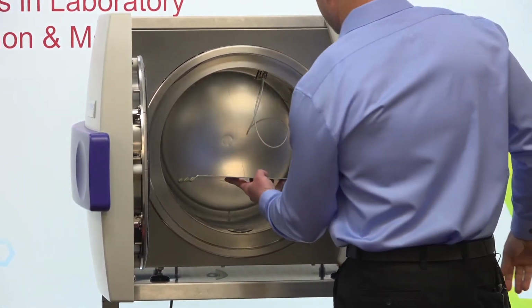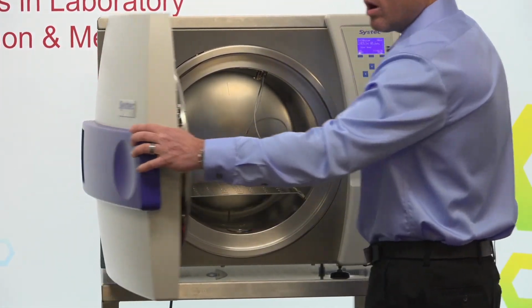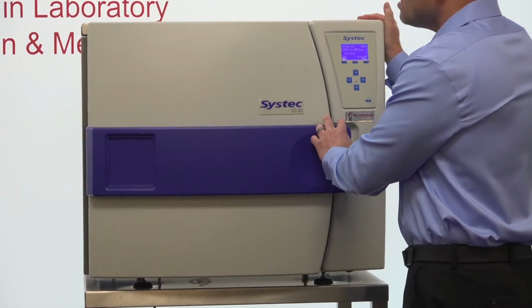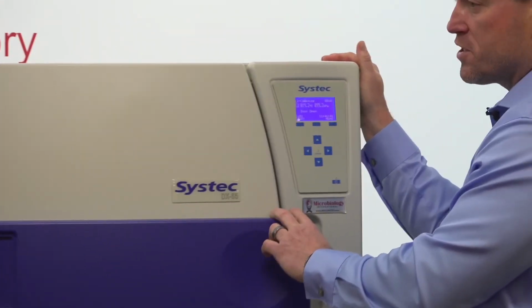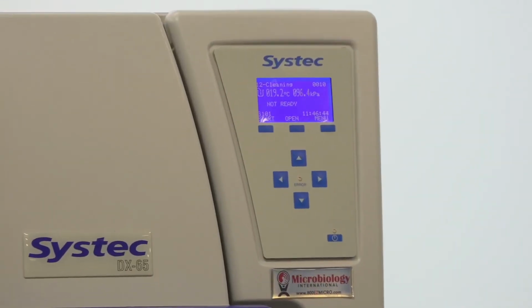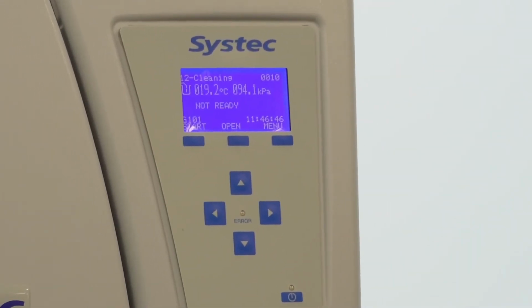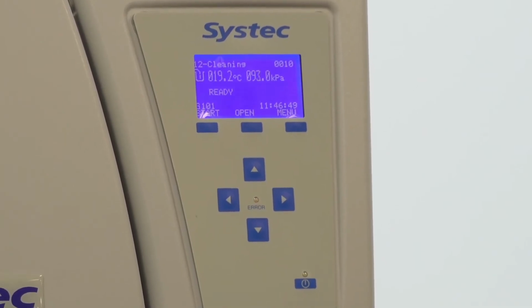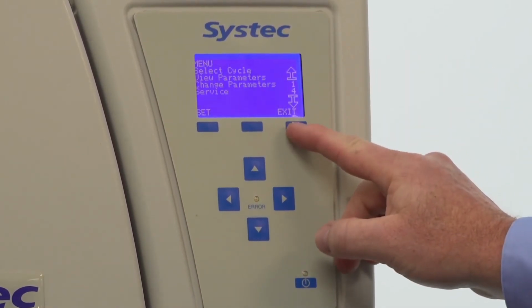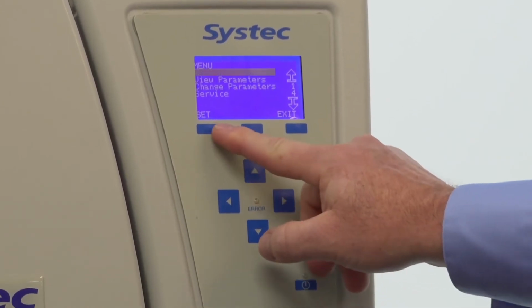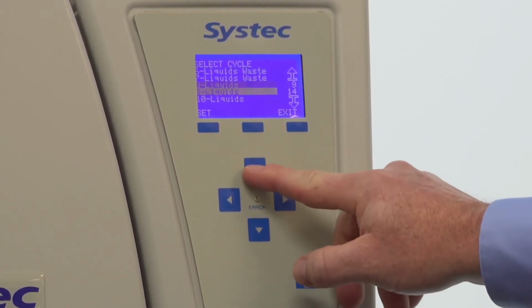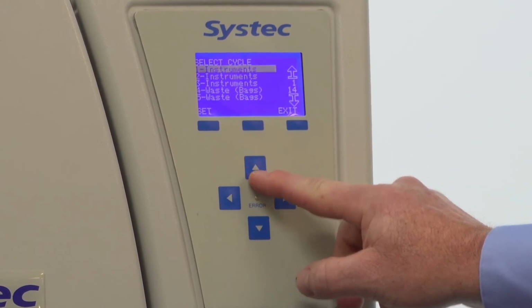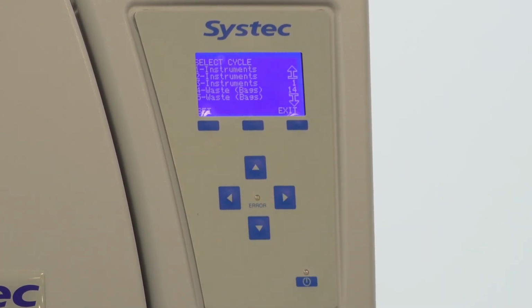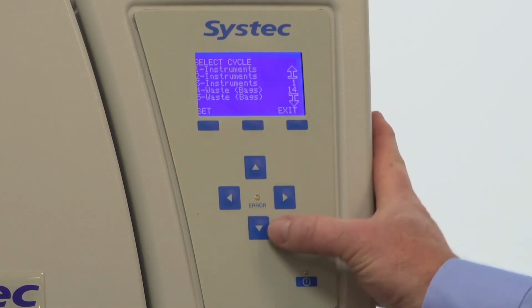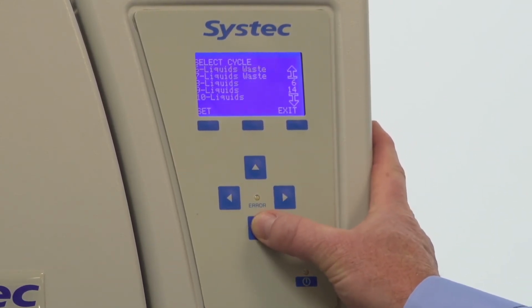Now we'll go through a little bit of the programming here, which is different than what is going to be on the HX series. Very similar layouts to cycles, but again with the keypad and not the touchscreen, there are a few less items that we have access to. If you go to our menu for this instrument, this has a different cycle layout. As standard, it will have 12 different cycles: 3 instrument cycles, 2 waste bag cycles, 2 liquid waste, and then 4 liquid cycles, and then finally a cleaning cycle.